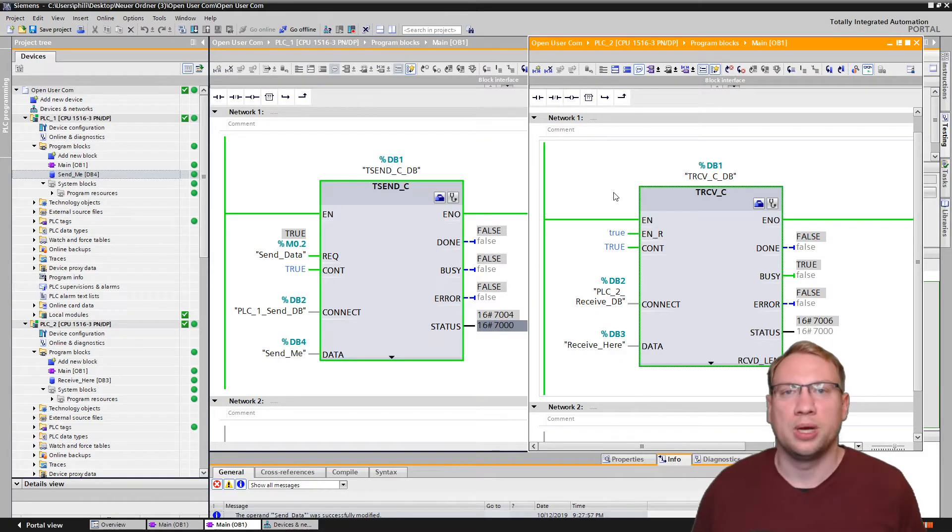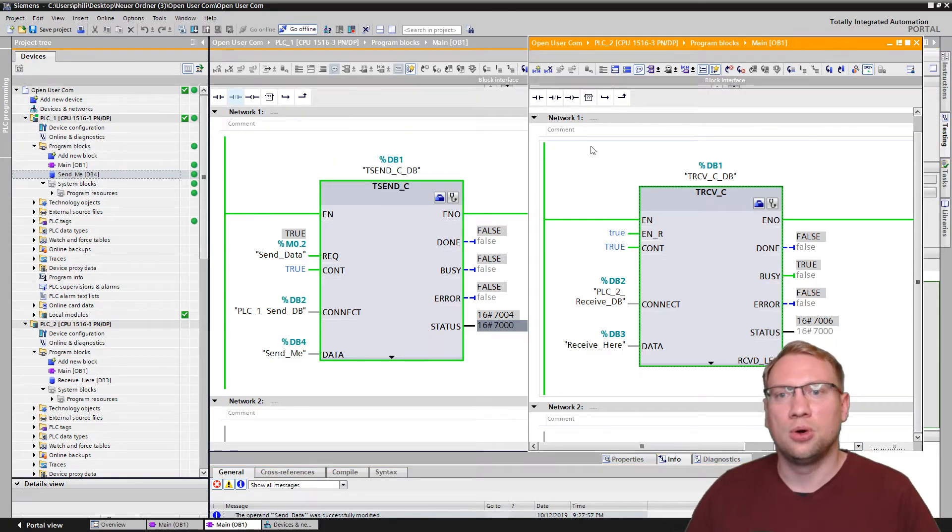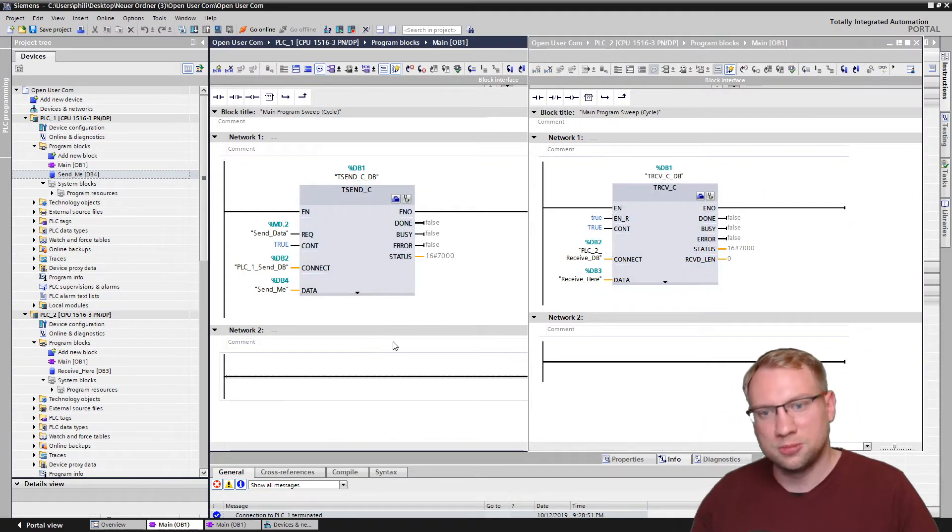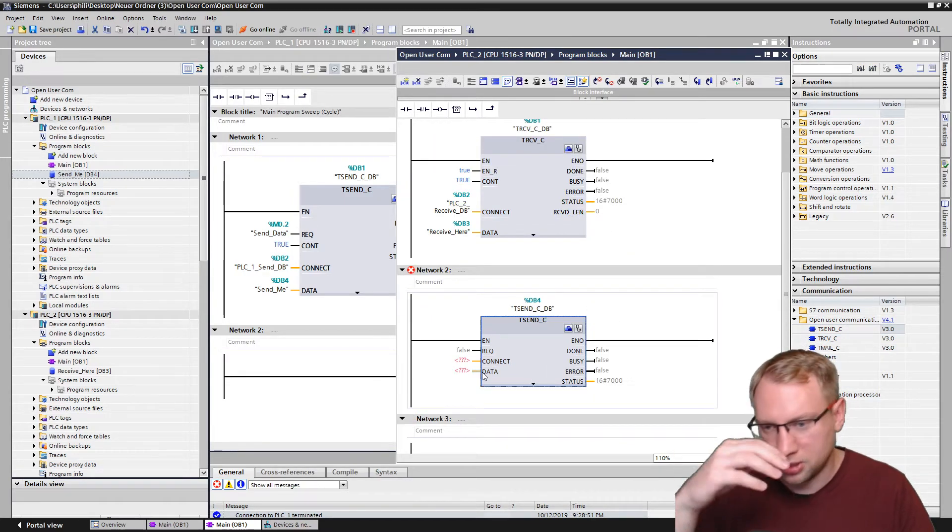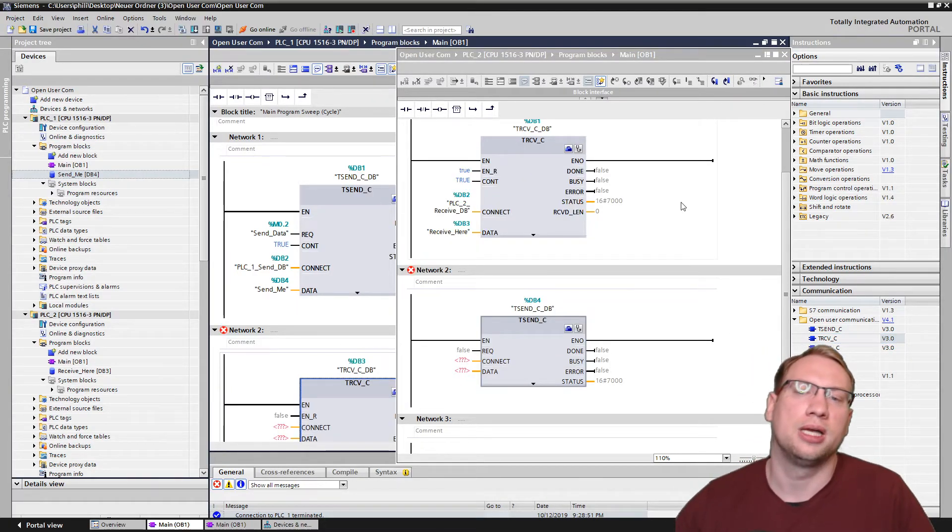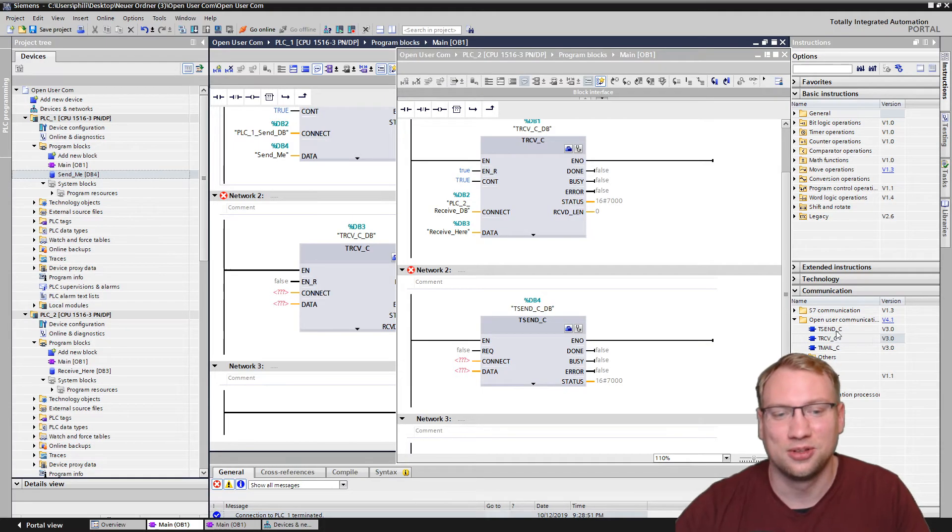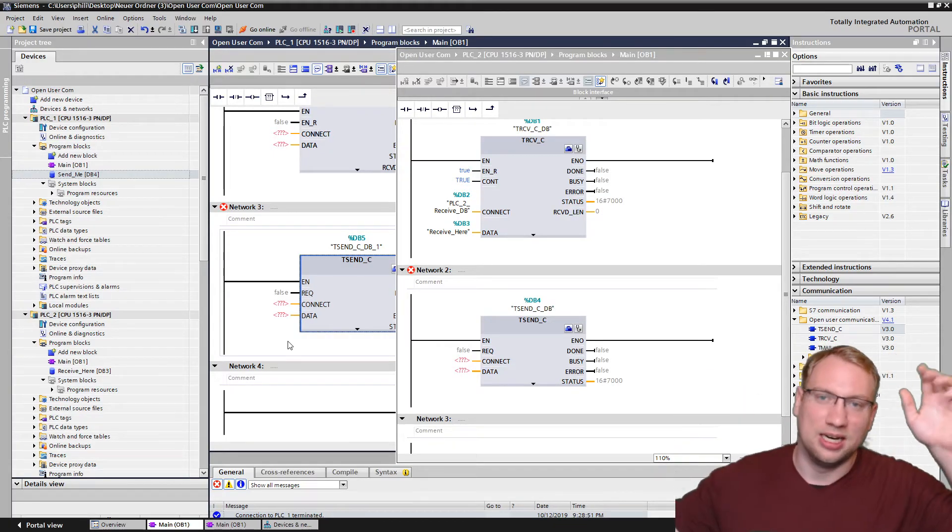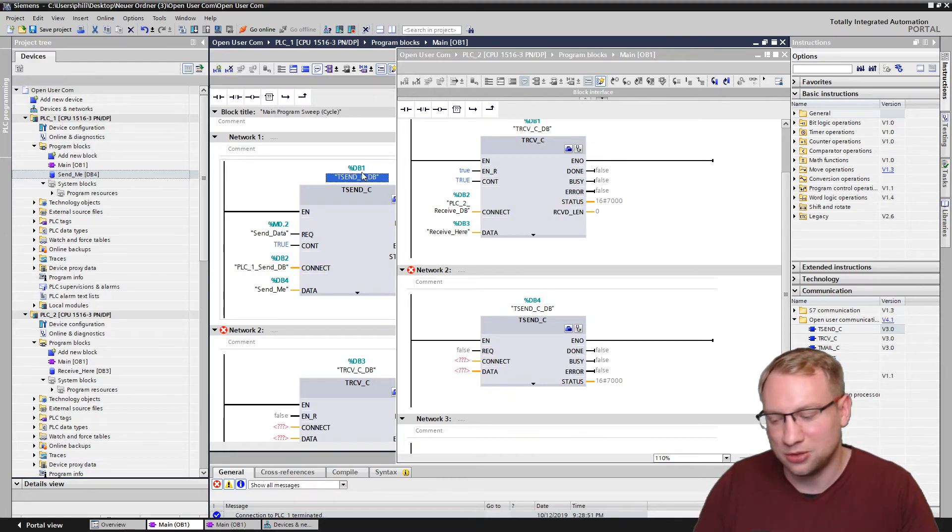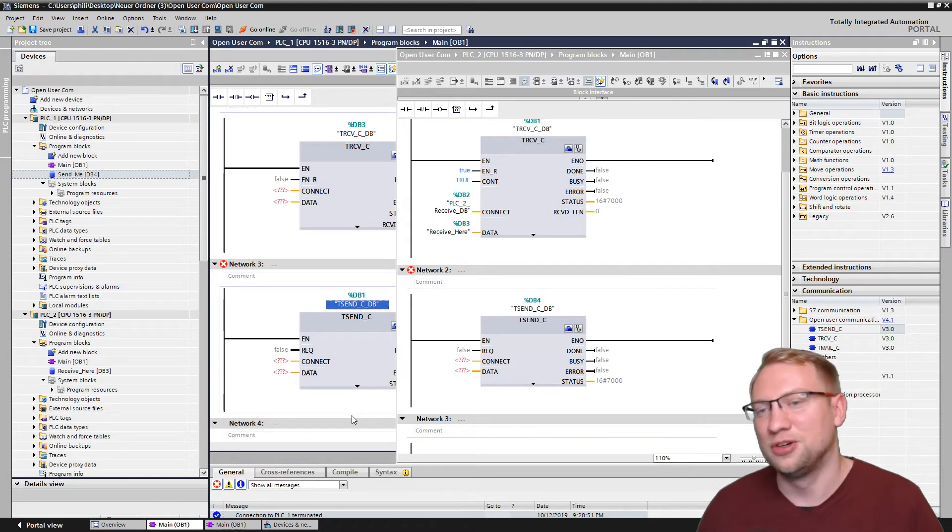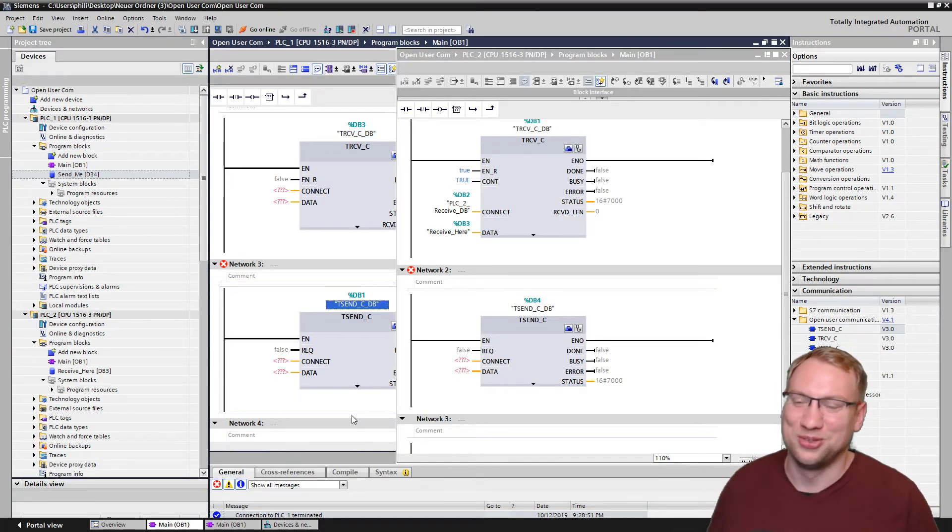So this here is the easiest way for me to send data from one PLC to another. If I would have a third PLC, or if I also want to send data now from the second PLC to the first PLC, make a guess what I do. In my second PLC, I take a TSEND block, but I configure it with all the stuff that I want. In my other PLC here, I would put the TRECEIVE block. I configure it as I want, and done. If I want to connect to a third PLC, if the first PLC wants to send to the third PLC, a TSEND block in the first PLC, here we go, put the data there, and put the connect data, and so on, done. Just copy, paste, and repeat. The only thing, when you copy and paste, make sure that those databases are unique. Don't have database one here and also database one here. This won't work, of course, but that's instantiation, that's a different video, which you could check out on my channel about data blocks, I think, no functions, and functions blocks, and how to use them, how to reuse them.